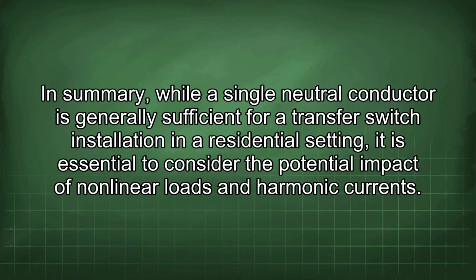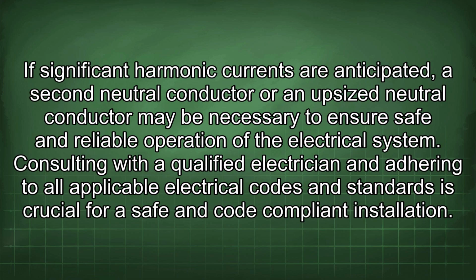In summary, while a single neutral conductor is generally sufficient for a transfer switch installation in a residential setting, it is essential to consider the potential impact of nonlinear loads and harmonic currents. If significant harmonic currents are anticipated, a second neutral conductor or an upsized neutral conductor may be necessary to ensure safe and reliable operation of the electrical system.